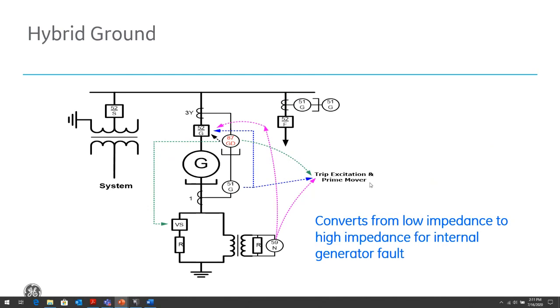The other type is a more complicated grounding scheme, which we refer to as a hybrid ground. As the name suggests, it's a combination of a high impedance ground and a low impedance ground. Normally, the generator is operating with the vacuum switch, the VS, closed, so the generator is normally grounded through a low impedance resistor. When there is a ground fault, the ground detector, like the 87 ground differential, will trip quickly. It will open the generator breaker and open the vacuum switch to limit the ground fault current. So now it goes from a low impedance ground to a high impedance ground. It limits the damage caused by the ground fault by turning it into a high impedance ground, and then it can open the generator breaker.